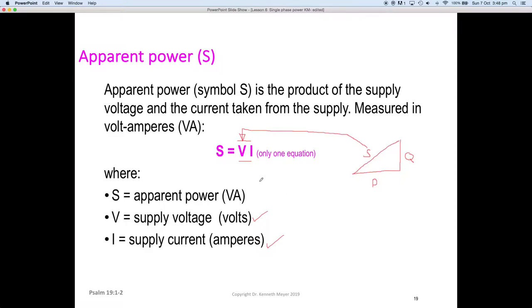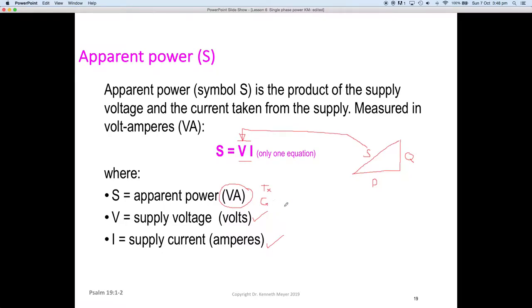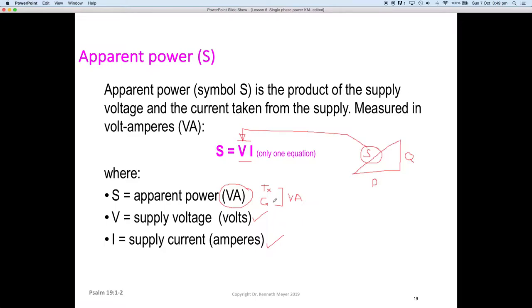Apparent power S is just the current multiplied by the voltage, and the units we use are VA. All transformers — abbreviated TX — and all generators are rated in volt-amps, because that is the worst-case scenario. The hypotenuse of the triangle is always the worst case: S is always as big or bigger than Q, and as big or bigger than P. Therefore S is always the worst case, and we always size transformers and generators for worst case.